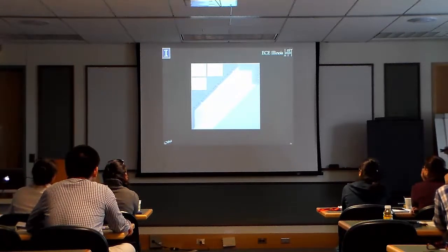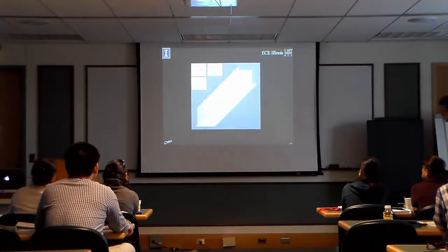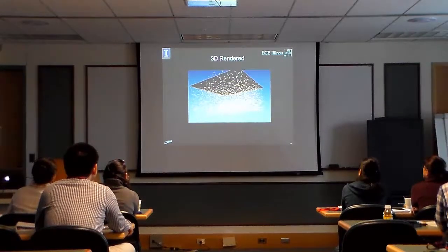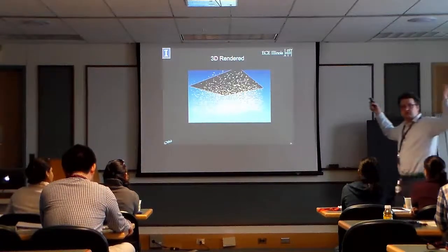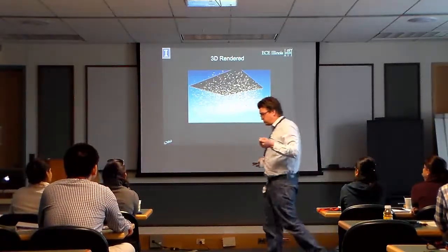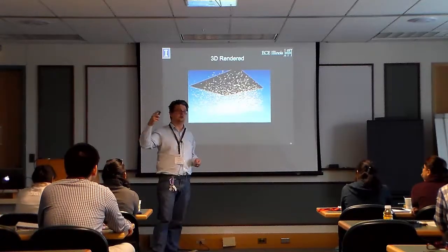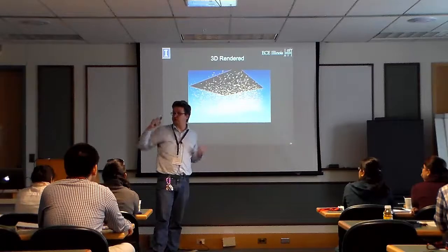Plane 3 is a little closer to the focus. They look a little more point-like. And when you run the algorithm, you get points, which is what they should look like. This is just rendered in 3D because it makes me happy, and it turns into that. So this solves the basic problem of the defocusing in OCT, and it means that you should not anymore worry about trading off between resolution and the distance over which you can reconstruct your image.